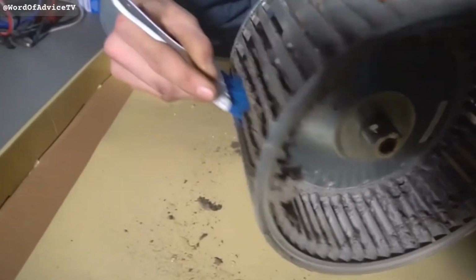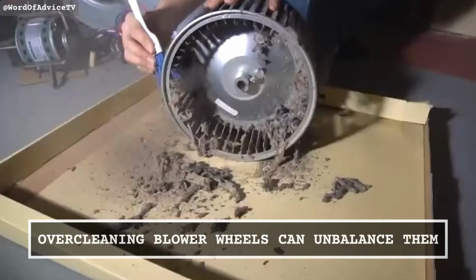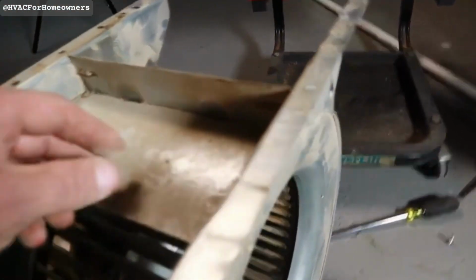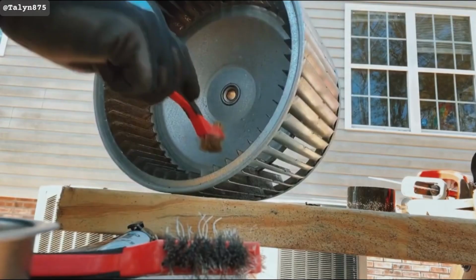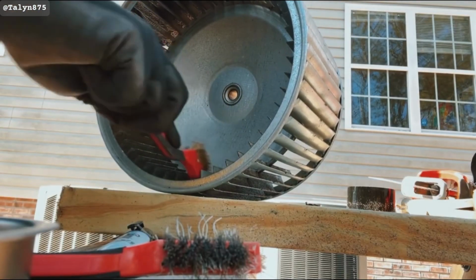Number 29. When you clean a blower wheel, the wheel needs to stay balanced. Dirt accumulation often happens unevenly, and aggressive cleaning can throw the balance off if you remove deposits from one blade more than another.